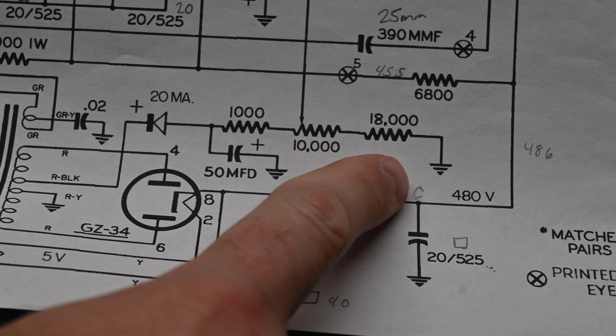Okay, before we install the inrush current limiter, I want to get a few more data points. So the multimeter is still connected to pin 8 of the rectifier at the moment, and we're reading 515 volts. I'm also curious to see what it reads on the other side of the choke, since the schematic shows 480 volts. So let's take a look at that. I'm going to move the probe.